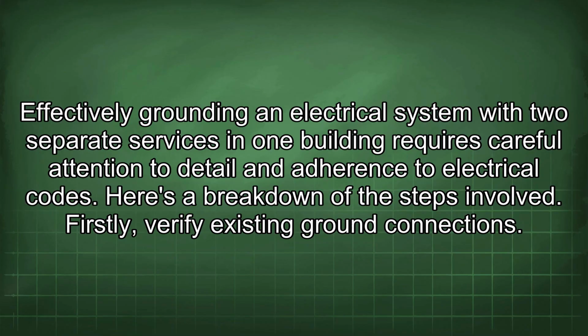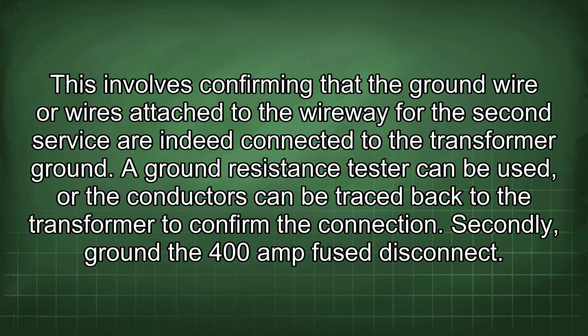Effectively grounding an electrical system with two separate services in one building requires careful attention to detail and adherence to electrical codes. Here is a breakdown of the steps involved. Firstly, verify existing ground connections. This involves confirming that the ground wire or wires attached to the wireway for the second service are indeed connected to the transformer ground. A ground resistance tester can be used. or the conductors can be traced back to the transformer to confirm the connection.